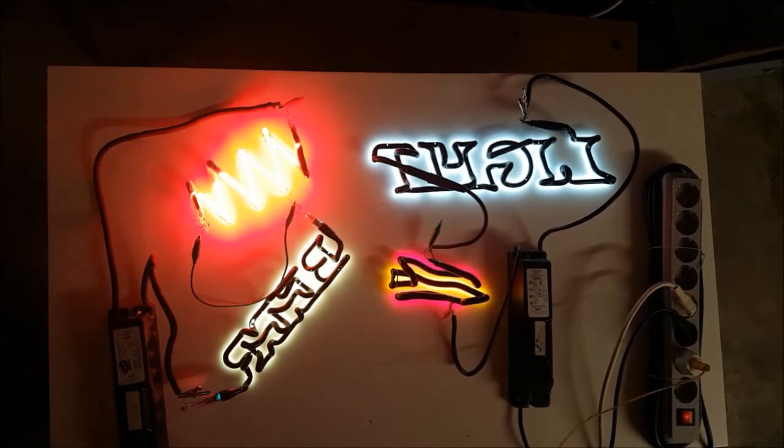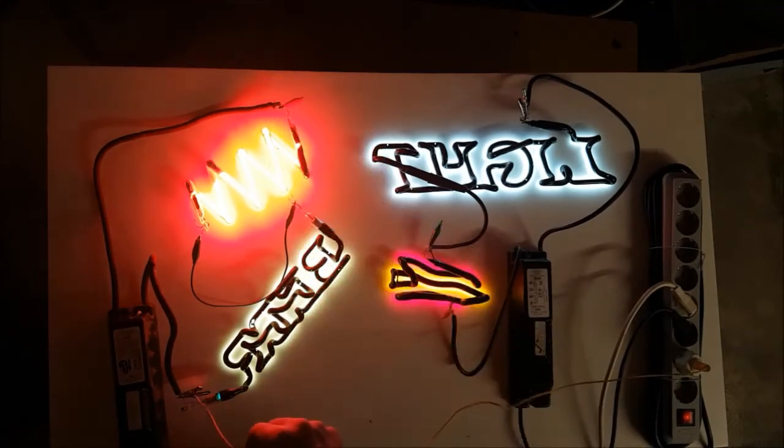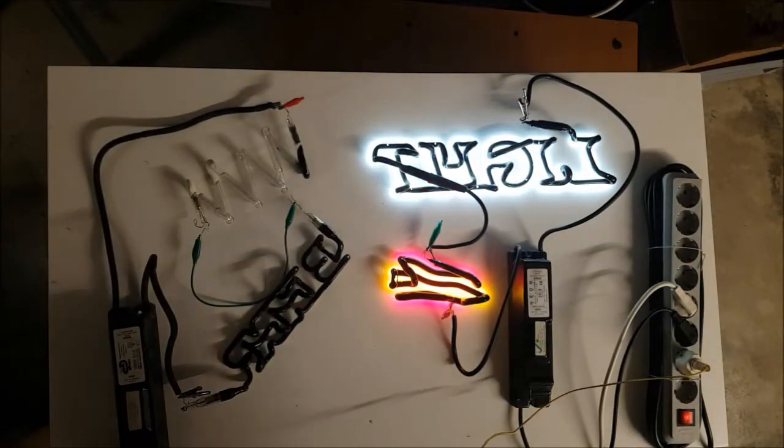Now if I do the ground fault test on the suspicious transformer, you will see that it does not shut off when I put the ground to this lead coming out of it. It does shut off when I put it to the other lead. So something's wrong on this side.